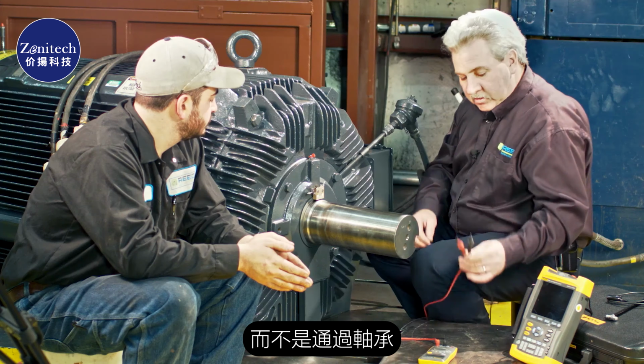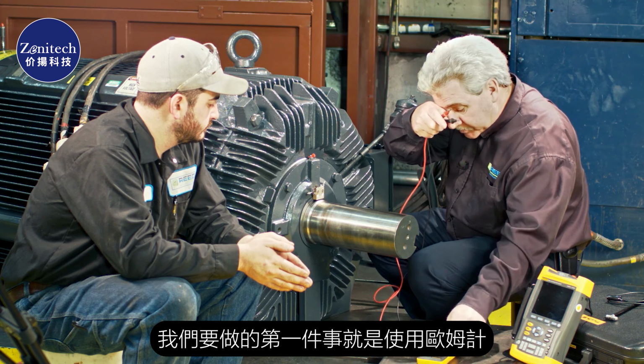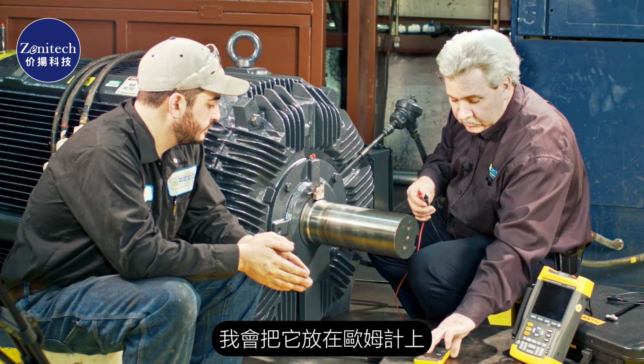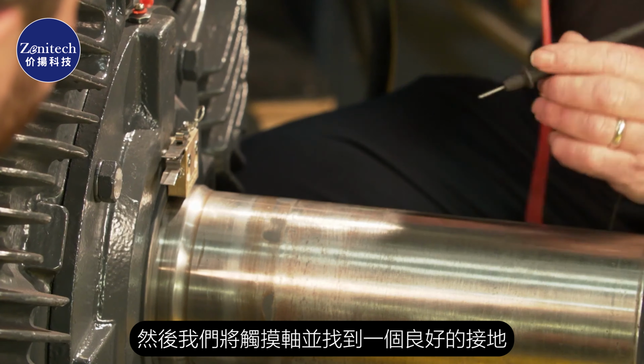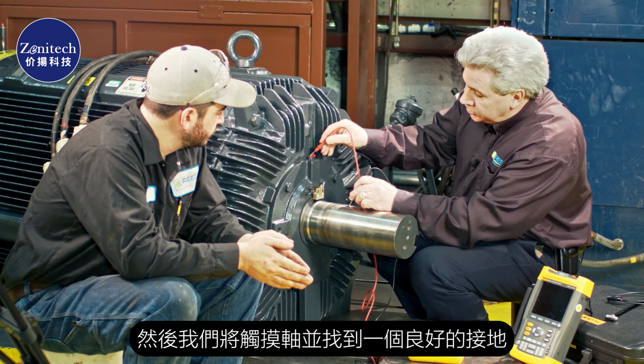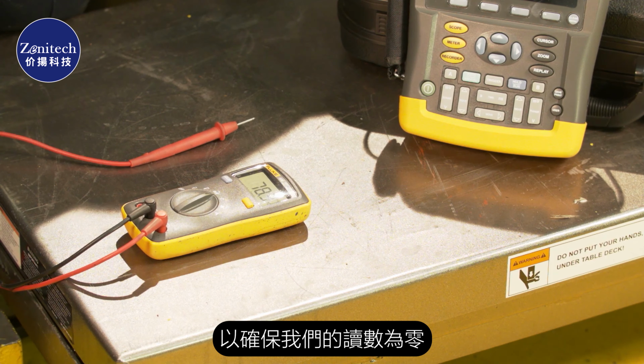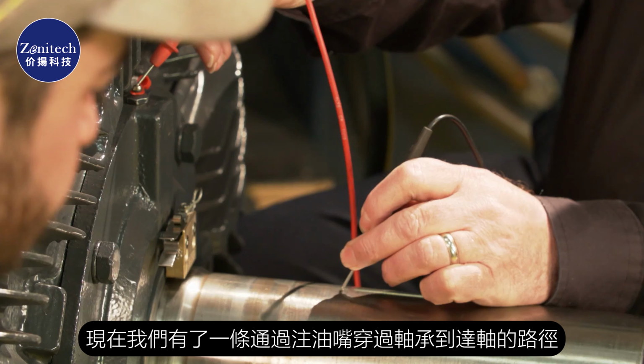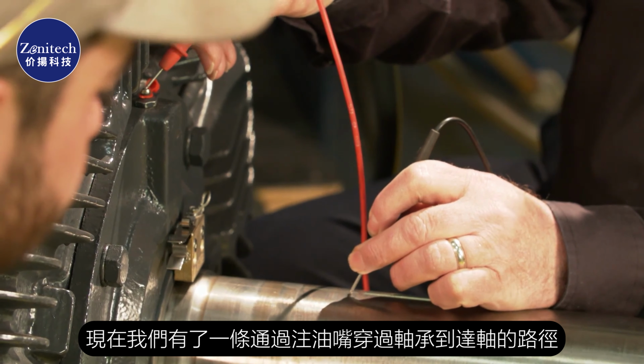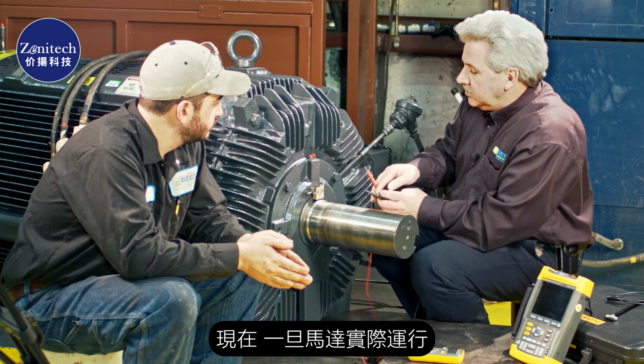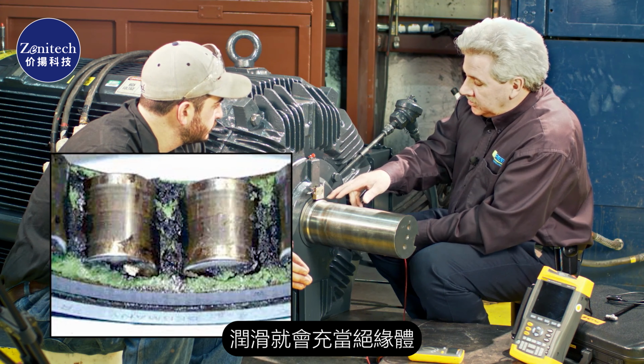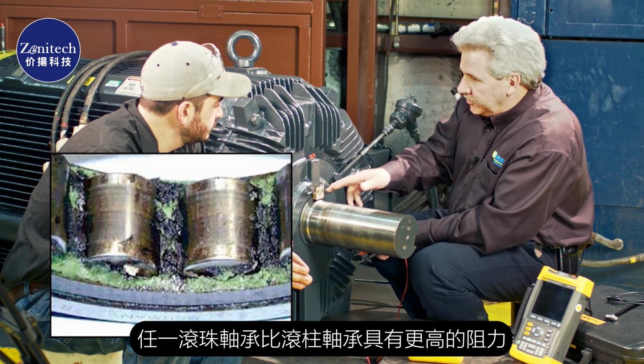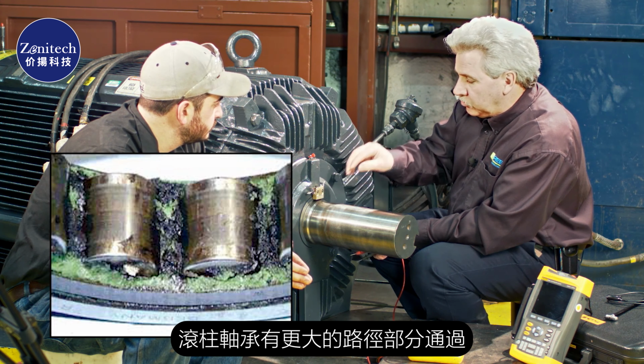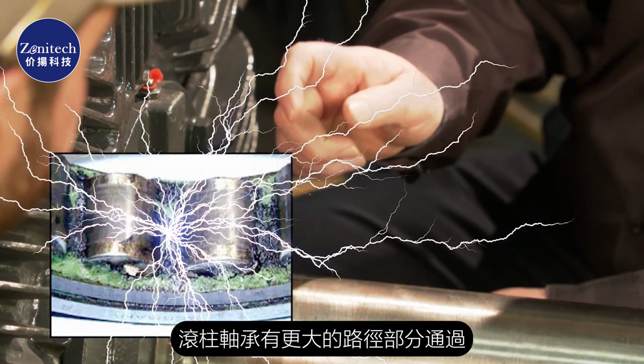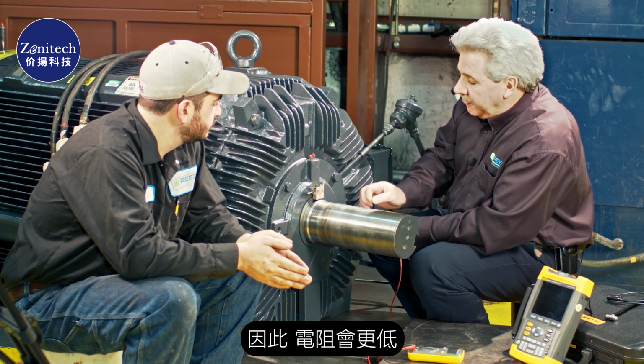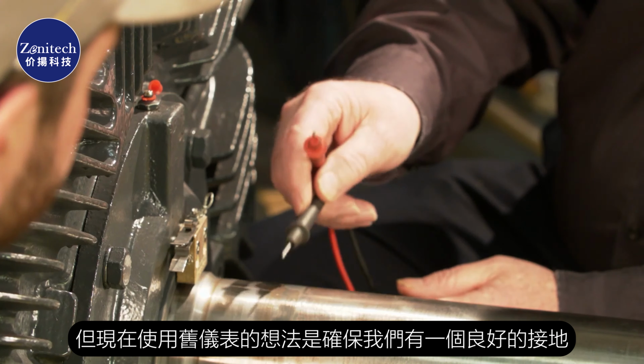the bearing. One of the first things that we're going to do is take the ohm meter, put it on ohms like that so you can see, and then we're going to take and touch the shaft and find a good ground to make sure that we have a zero reading. So now we've got a path through the Zerk going through the bearing to the shaft. Now once the motor's actually running, the lubrication acts as an insulator. Being a ball bearing or a roller bearing, either one. Ball bearing has a higher resistance than the roller bearing does. Roller bearing has a bigger path for it to pass through, so the resistance level will be lower. But the idea of using the ohm meter right now is to make sure that we've got a good ground.